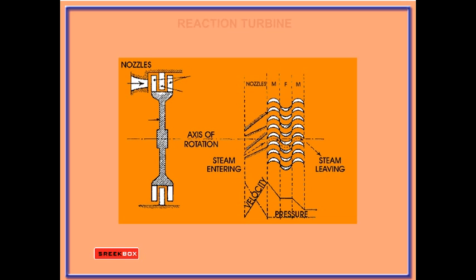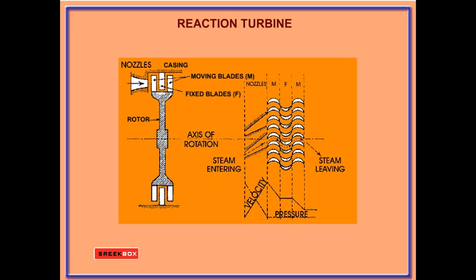A reaction turbine consists of a wheel or rotor, casing, and fixed and moving blades. Equal numbers of fixed and moving blades are attached alternately to the casing and the wheel respectively. The fixed blade is similar to a nozzle, where velocity increases with a decrease of pressure.